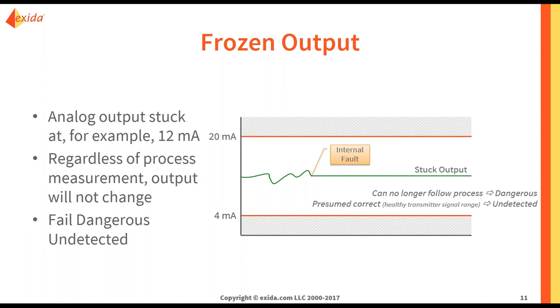First, you might have a frozen output. In this case, the analog output is stuck at, for example, 12 milliamps. Regardless of the process measurement, the output will not change, which means that your safety instrumented function cannot respond to a hazard. We call this failed dangerous undetected. In most cases, that is what it is going to be classified as. You will not know that there is a failure because it is not out of range, and it is not following the process value anymore. In some cases, if you have external comparison, this could be classified as a detected failure. However, in the SERH, you are going to find these failures under failed dangerous undetected.